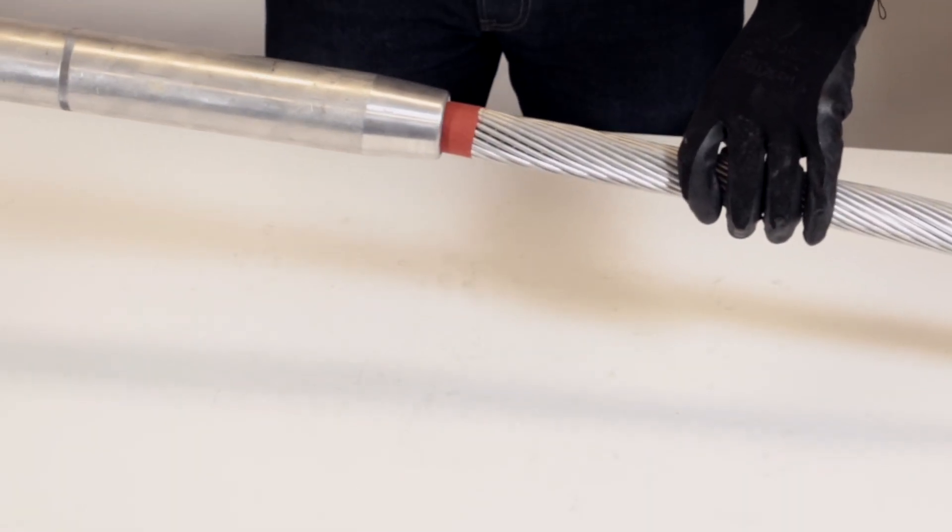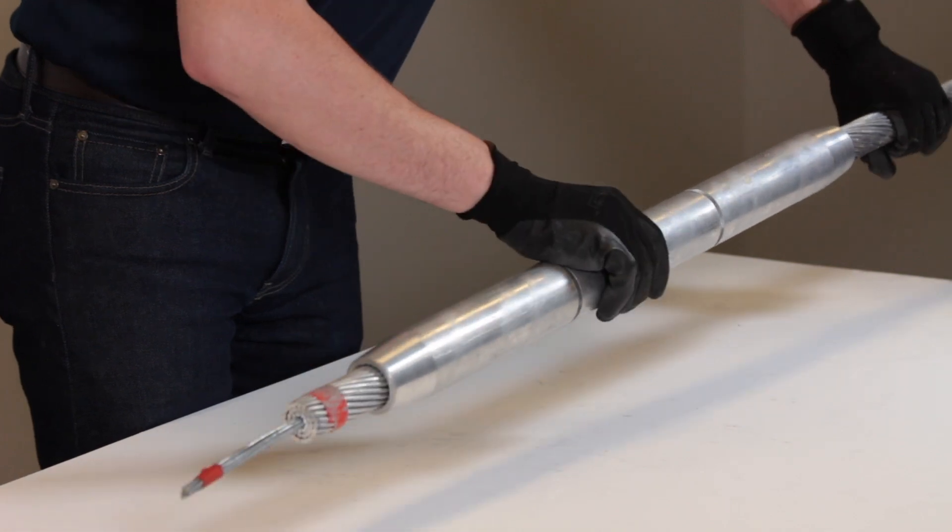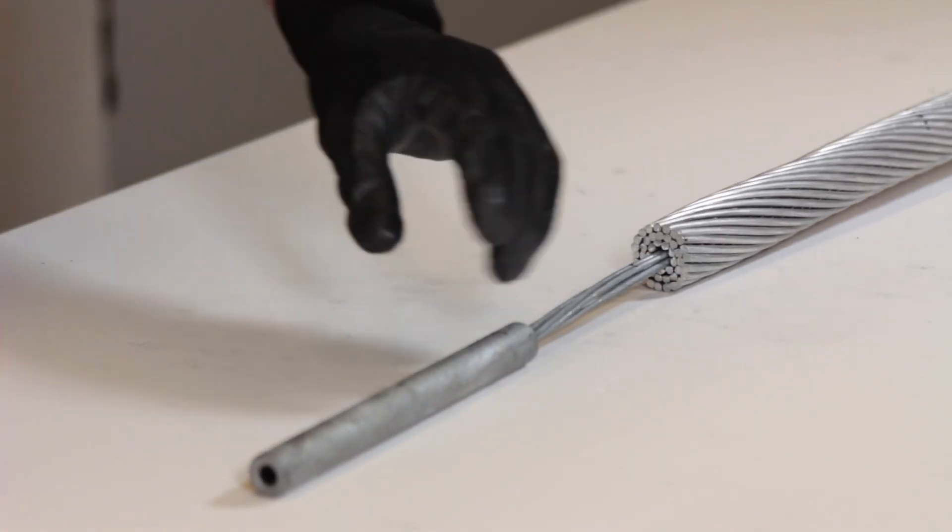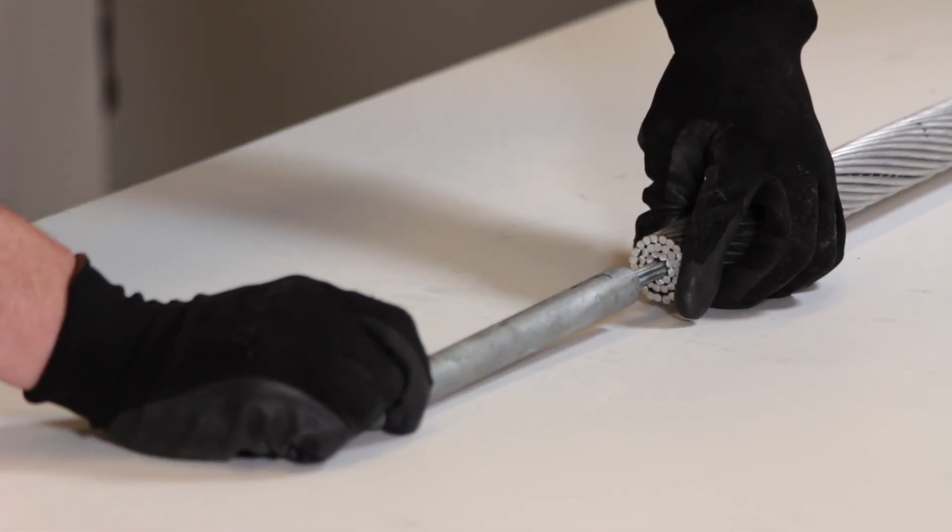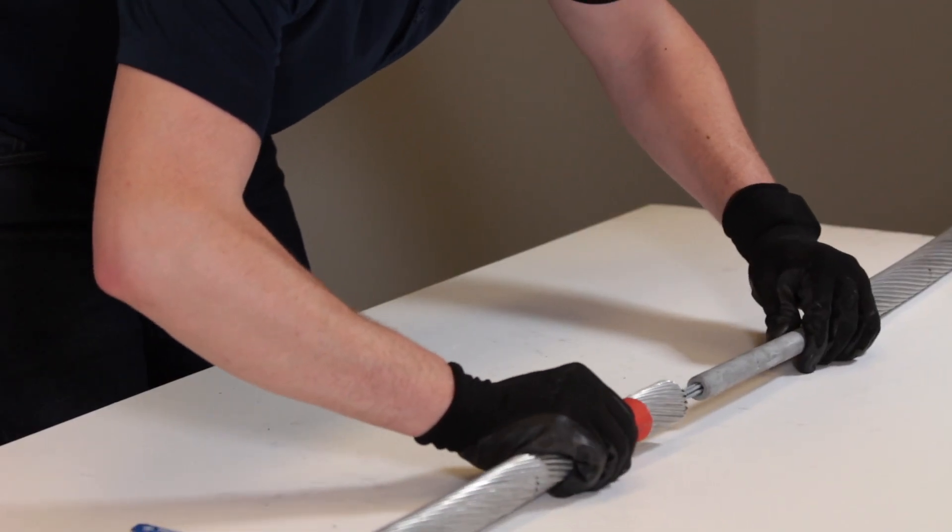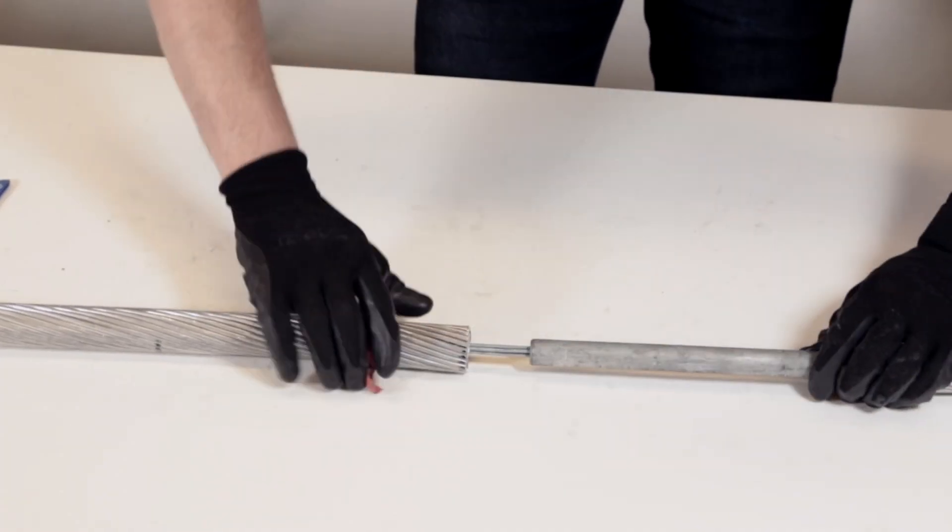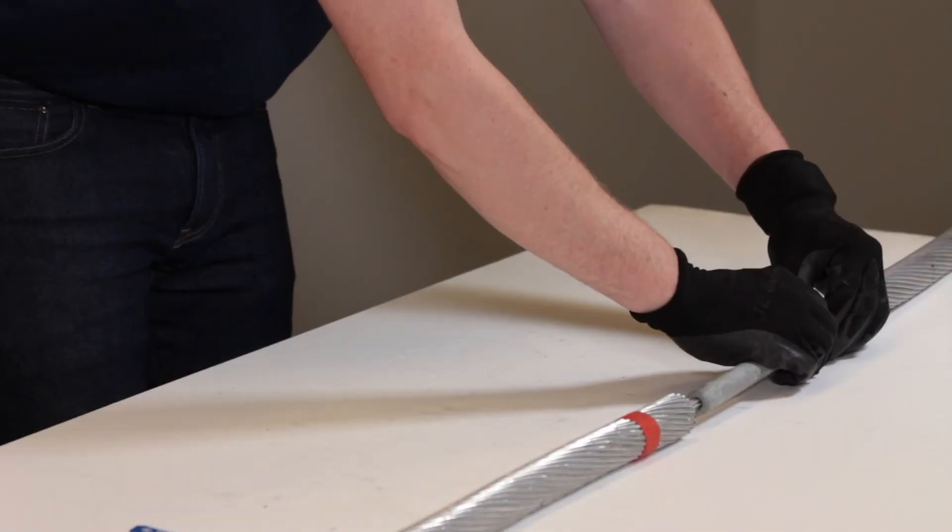Slide the aluminum splice body all the way onto the conductor past the exposed steel core. Remove the tape from the conductor core and insert it into the steel core splice, lining up the end with the mark previously made on the strands. Repeat this step with the other conductor and ensure that the core splice is properly centered.